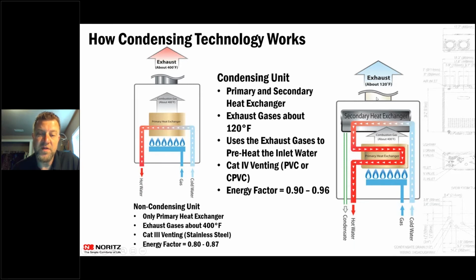So this will give you lower stack temperatures, so you can vent in category 4 venting, which is PVC, CPVC, or polypropylene. This also gets your energy factors up, which is from a 0.90 to a 0.96.